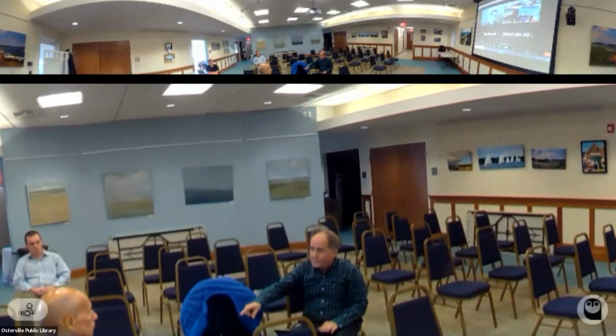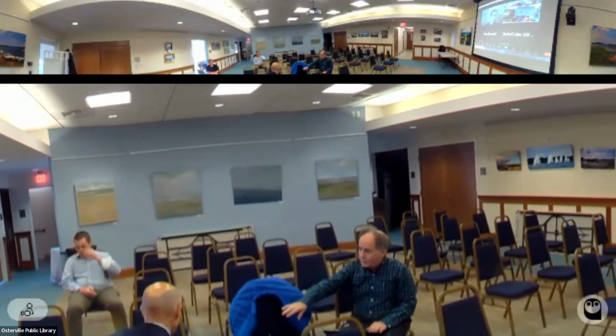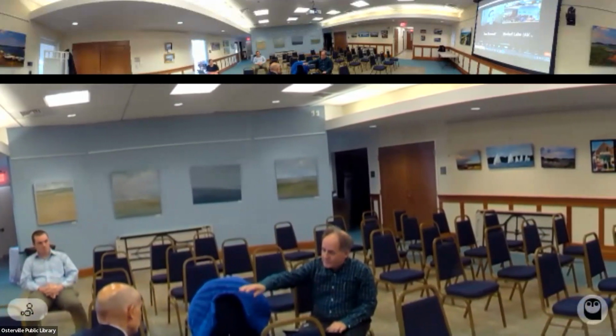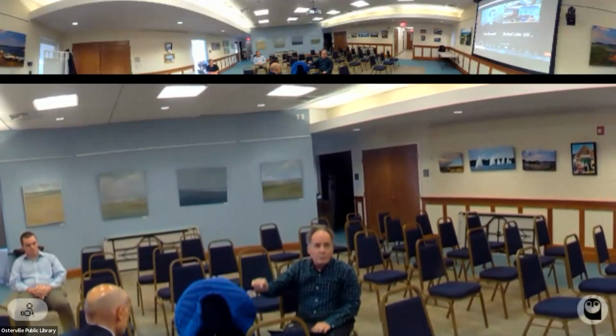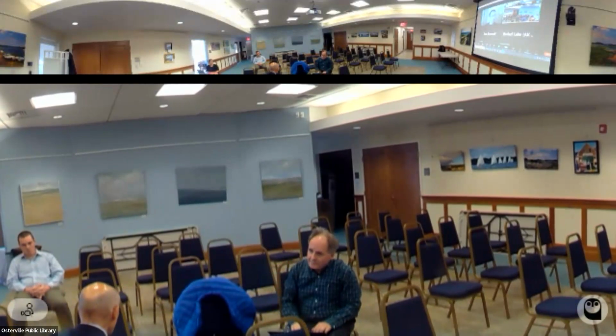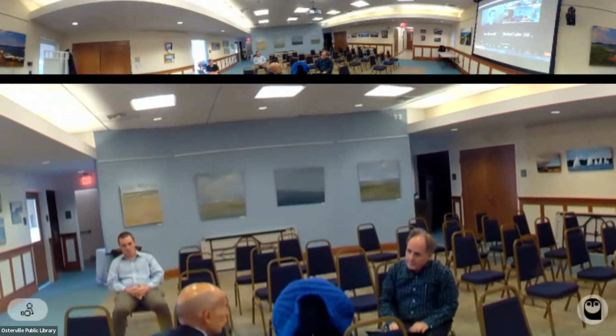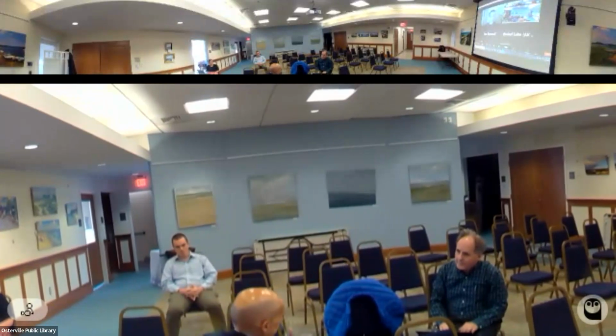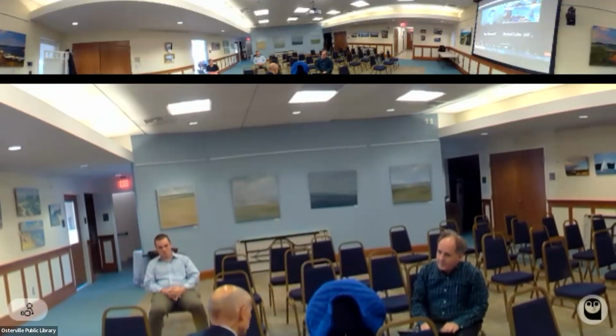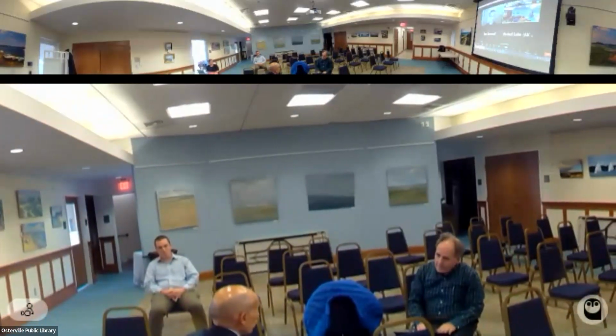So one of the rows of 3 cables will be dormant, right? Or you got a total of 12 cables and it's 3 by 4. Will one row of the 3 be not live, or will they alternate? There'll be 3 dormant conduit in the duct bank. They're not in a specific row. They were basically optimized to balance out the system by way of ampacity, temperature, and EMF. We could send you something to show you where they're located.